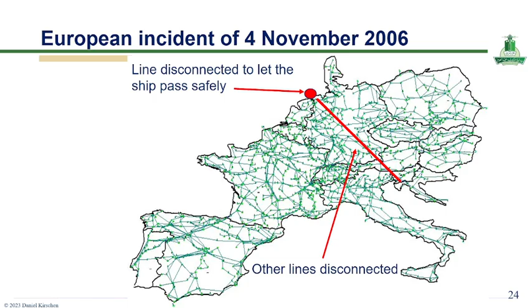Okay, the European incident of 4 November 2006 illustrates how tightly interconnected modern power systems can be vulnerable to cascading failures. What initially began as a routine and planned switching operation quickly escalated due to unexpected power flow redistribution and overloads on neighboring transmission lines. Protective devices then acted to disconnect additional lines, which further increased stress on the remaining network. This chain reaction led to a widespread disturbance affecting large parts of Europe and demonstrated the importance of accurate system planning, real-time monitoring, and coordinated control actions in maintaining stability in large interconnected grids.